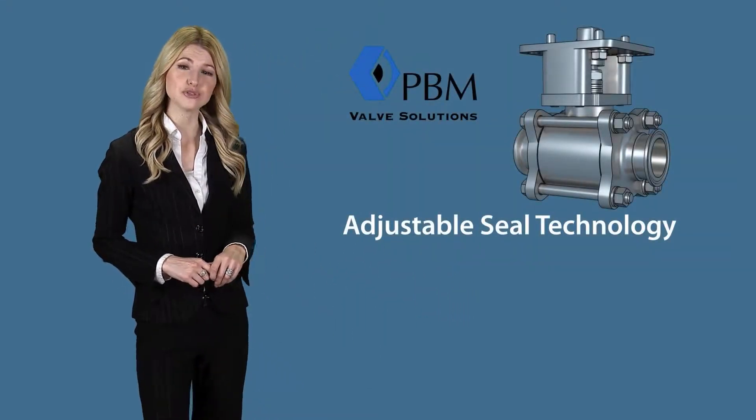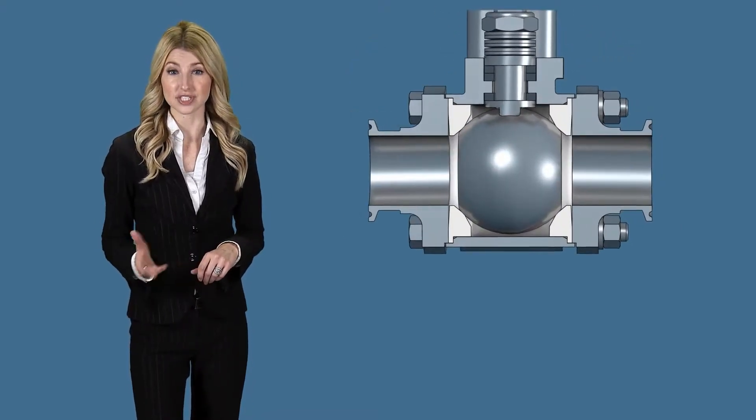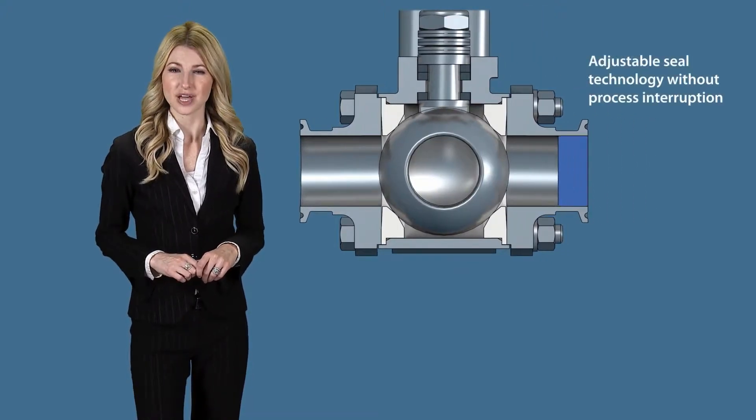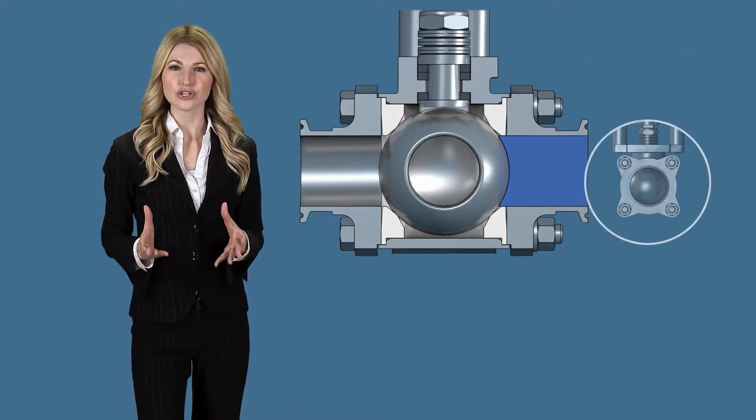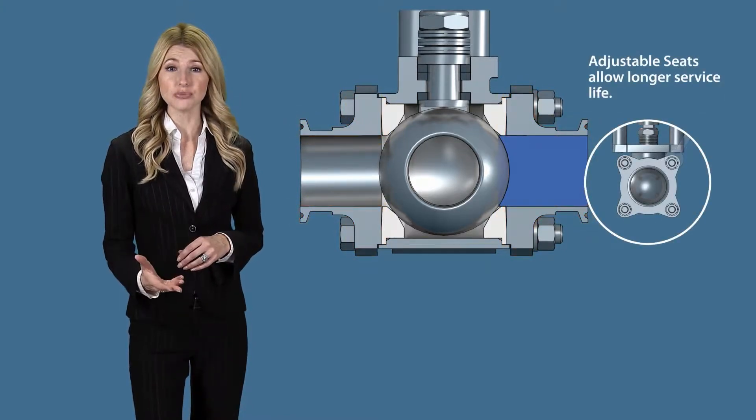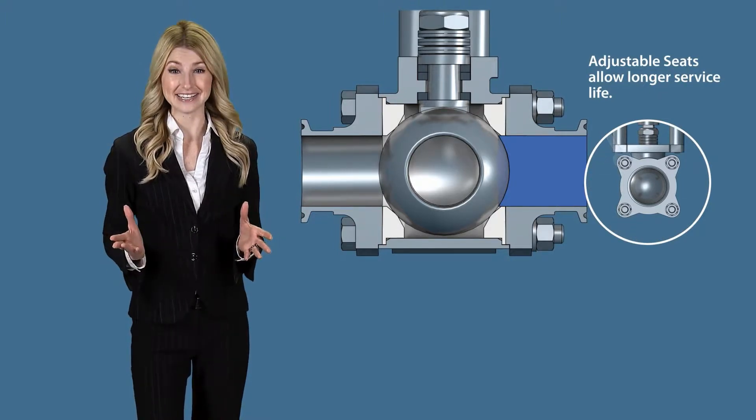Adjustable sealing technology allows you to reseal the valves in the event of leakage, similar to tightening a packing nut on a valve to stop seepage. We apply the same principle to our valve's body bolts, which bring the seats incrementally closer to the ball to compensate for normal wear, allowing multiple adjustments over the life of valve seats and seals. Simply innovative.